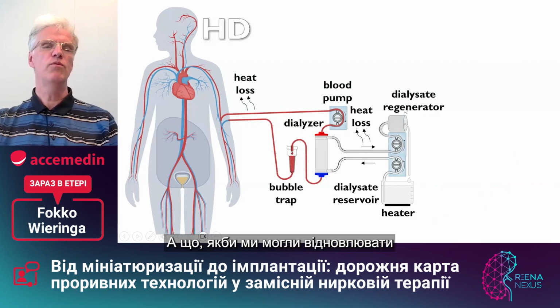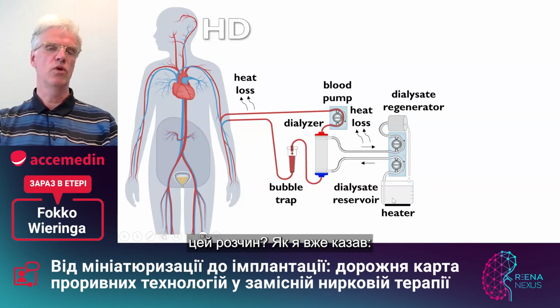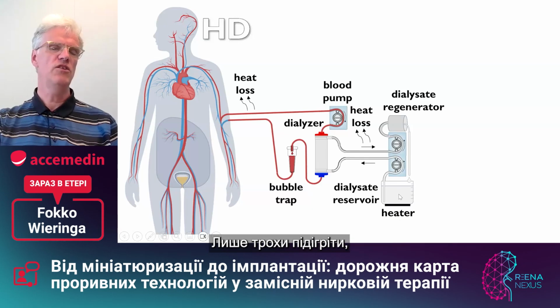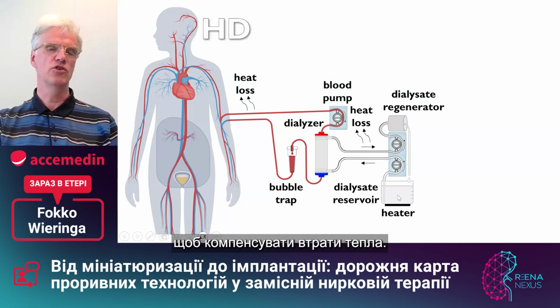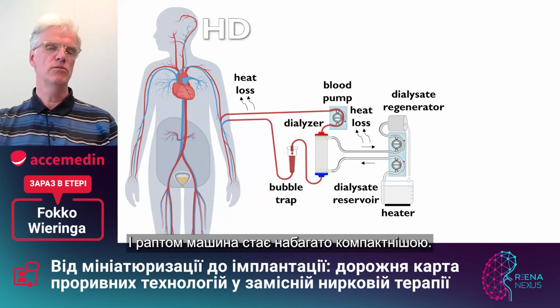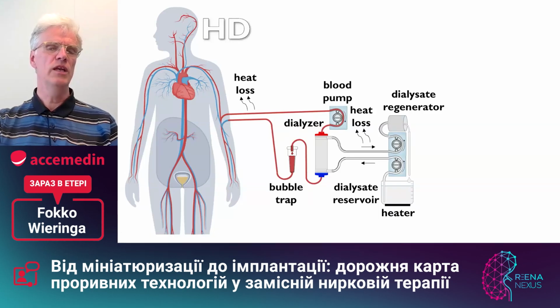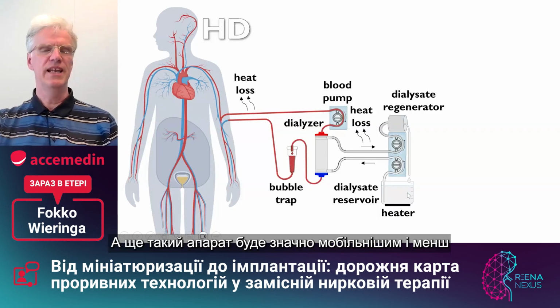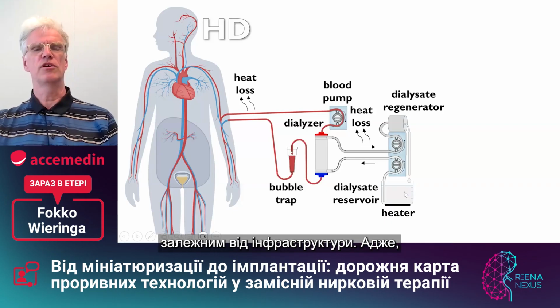But what if we would regenerate this? So like I said, let's regenerate the dialysate. First of all, you'd need much less fluid and also much less electricity because it's already warm. You regenerate it, but it doesn't cool down fully there. You only need to heat it up a little bit to compensate for heat loss. Suddenly your machine becomes much more compact and also much more transportable and less dependent on infrastructure.